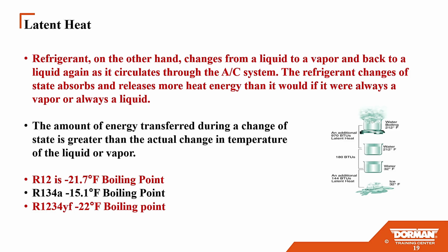It takes a journey. The refrigerant's change of state absorbs and releases more heat energy than it would if it were always a vapor or always a liquid. This relates to latent heat, gauged in British thermal units — about 970 BTUs of latent heat. Water boils at 212 degrees, but to change its state you have to add that extra amount of BTUs. That's when it changes state to vapor. If you were to use a temperature probe on that water, it would still read 212 degrees.